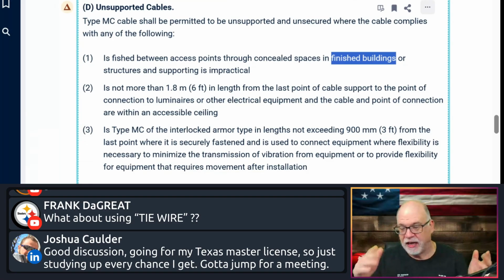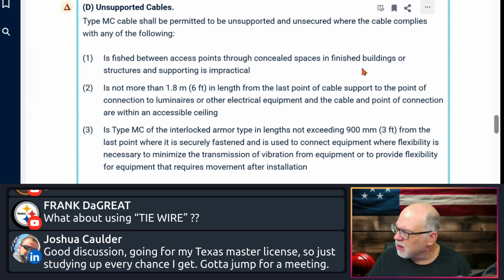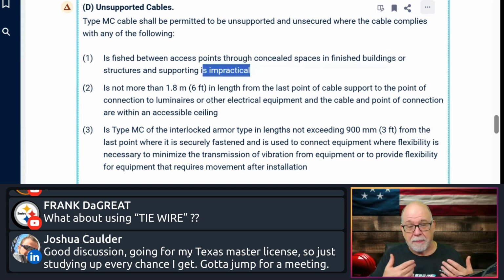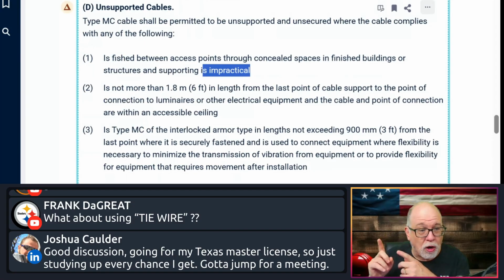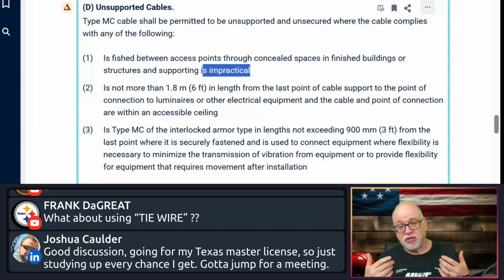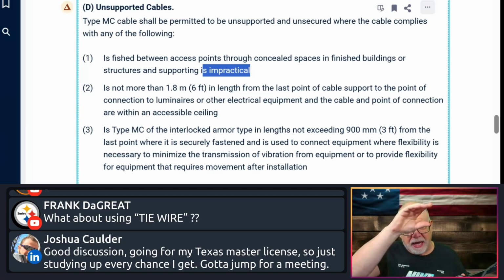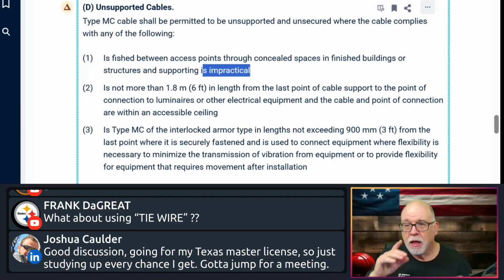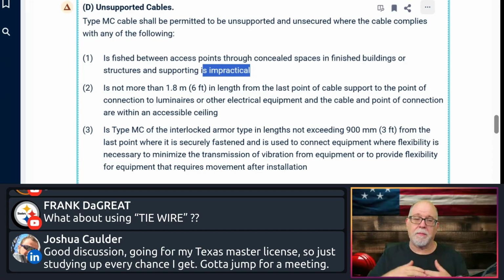It's not finished yet. But then it says, or structures and supporting is impractical, which means that maybe something has happened. And at this point, a piece of equipment may have been put in. It's not a finished building yet, but it says, or structure or supporting is impractical. Maybe the timing screwed up and they put in a piece of equipment that you can't get behind, but you can get from top to the bottom and you could fish it in. Double check with your AHJ because of using this one. Make sure they don't have a problem.